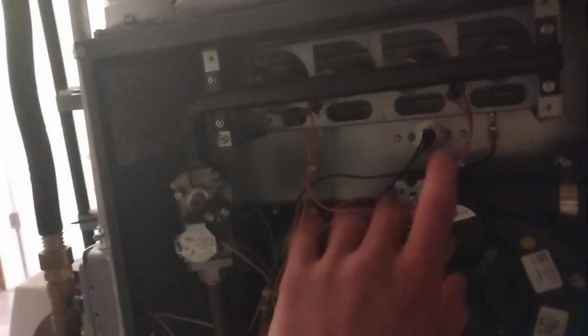Just a month ago, when I did my own little inspection - because every fall I do this, I open it up like this and let the whole thing run through - these flames here were all blue, completely normal. But just yesterday, some other servicemen came in here, and then we had rollout flame happening, which is the indication of a crack in the heat exchanger, and that's bad. We don't want our house to have that going on. We can't have that.